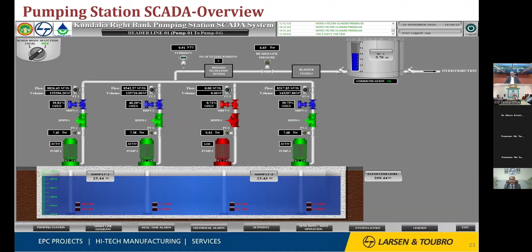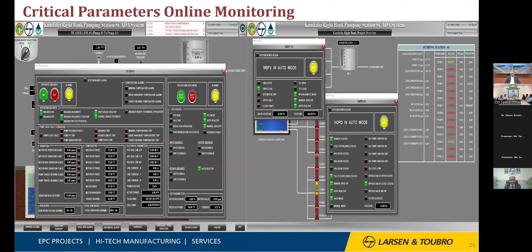Now, in this SCADA, the reason human intervention is minimally needed and it takes care of everything is that for the critical parameters we have kept sensors for vibration and temperature. Bearing temperature is monitored, current is monitored live, and all have preset levels. If any level goes out of range, first a hooter gives an alarm so the operator becomes alert that something is going on, and if it reaches the trip point, it will trip the system so that no damage comes to the system. So all the critical parameters are always monitored through our SCADA.